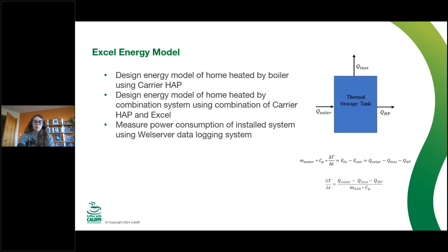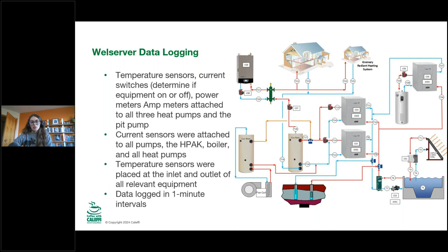So in terms of actually collecting data, like I said, we used a Welserver data logging system. We had temperature sensors and current switches, which determined if the equipment was on or off. We had power meters attached to all 3 heat pumps, as well as what we called the pit pump. The pit pump is the pump in the open loop ground source heat pump. And then temperature sensors were placed at the inlet and outlet of all relevant equipment, and data was logged in 1 minute. I think that's actually wrong. I think it was logged in 15-minute intervals. So the moral of the story is I had a lot of Excel data to work with, which was pretty fun.